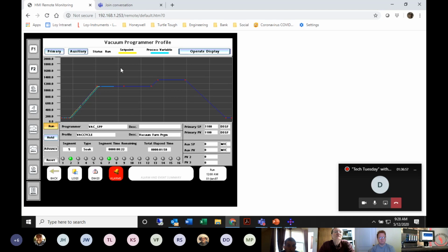The reason is that this screen was developed by Honeywell out of the box, where it not only tracks and trends the process variable and the set point, but it also pre-plots the entire set point profile on the trend screen. The pre-plot is what really takes a lot of engineering time if you were to do this from scratch, if anybody's programmed those before.